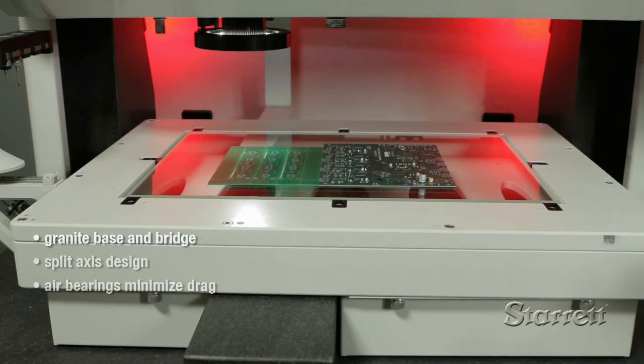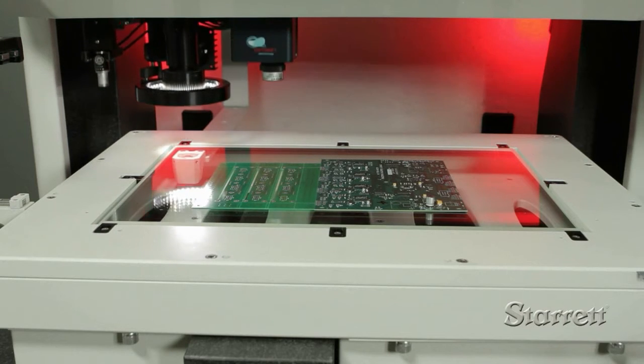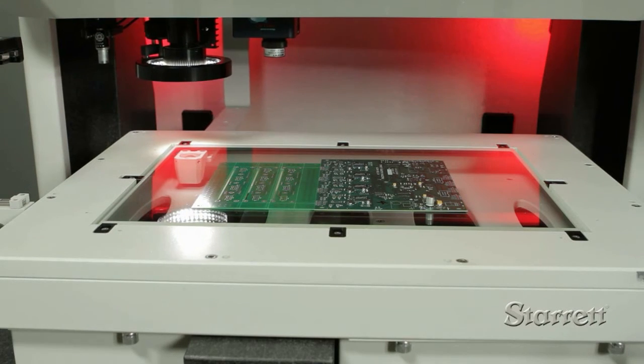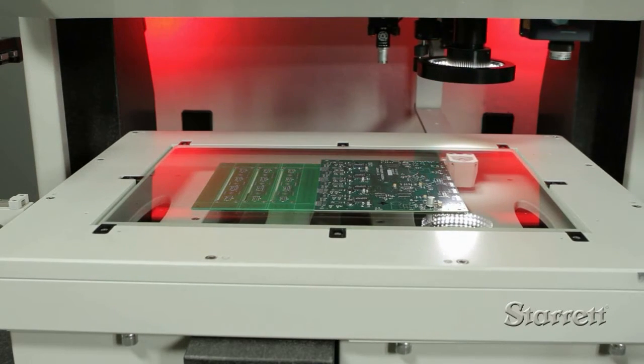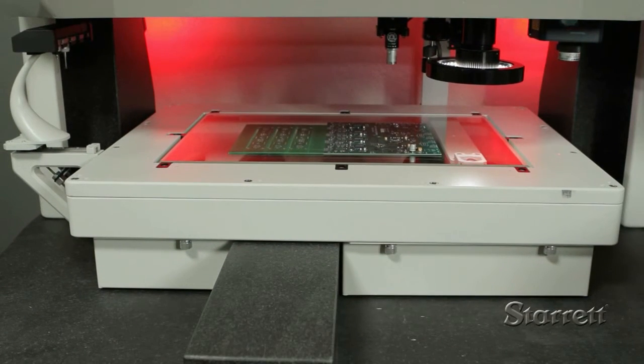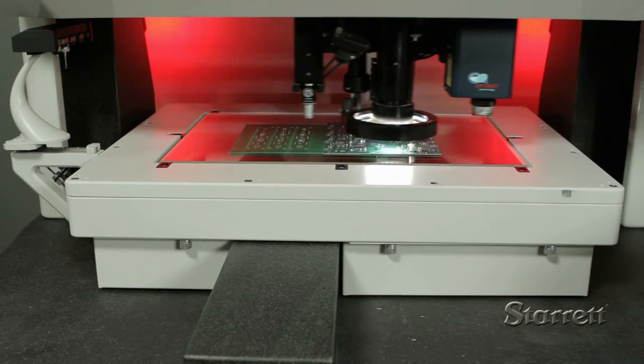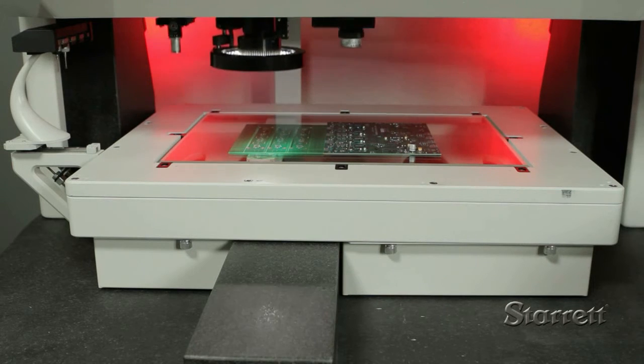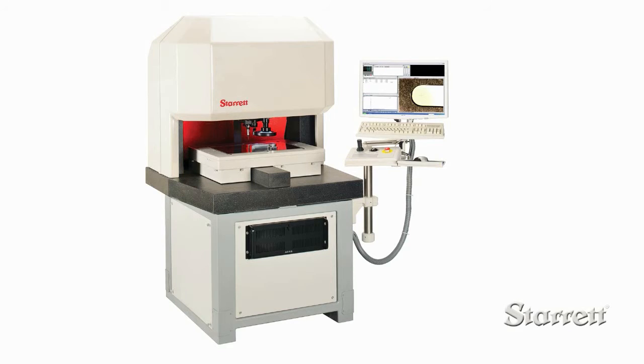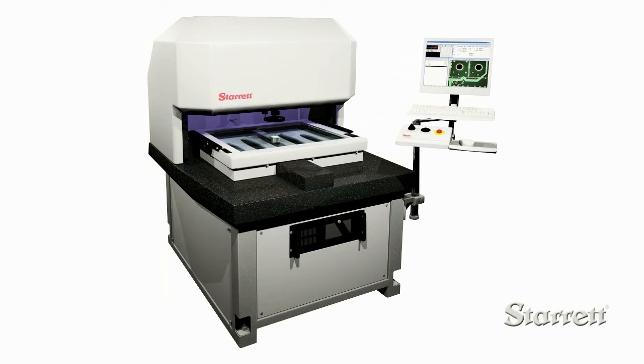LF systems are built with granite base and bridge construction, split axis design, and air bearings on all axes to minimize drag. Linear motors can move the axes up to 30 inches per second with exceptional accuracy and repeatability. This LF463 system has an 18 by 12 by 8 inch measuring capacity. Larger capacity systems are available up to 50 by 32 by 8.